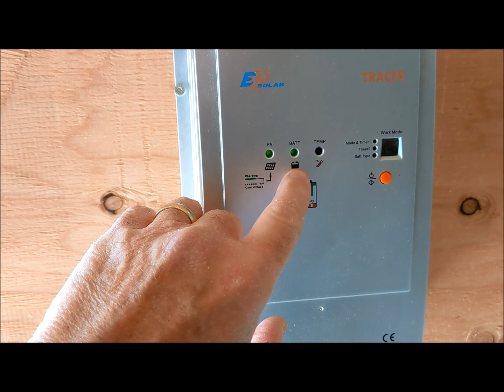One thing, when you start the solar array, you want to make sure that the charge controller is getting power from the battery first before you add the solar panel's input to the charge controller. So always turn on first the circuit breaker to the batteries, which powers up the charge controller. These are smart, so they know they can read the voltage, whether it's 12 volts, 24 volts, or larger if it's a larger charge controller. That's the reason the battery needs to be energized first.